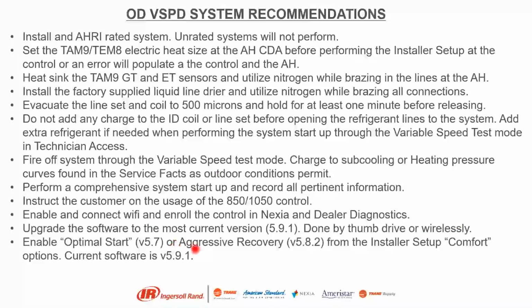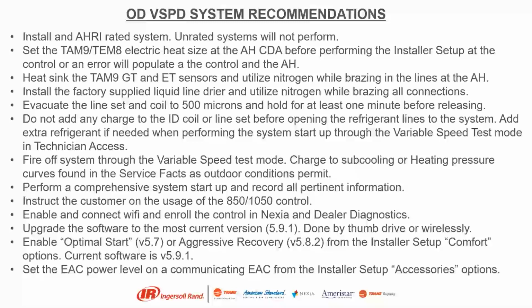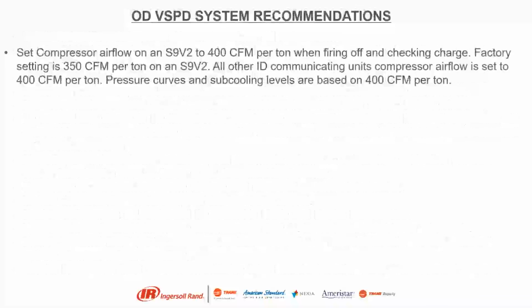Enable optimal start or aggressive recovery for heat strips. We do recommend setting that to aggressive recovery if we have heat strips, because it'll turn that heat strip on and satisfy the home quicker. Set the EAC power level on the communicating EAC. Set up accessories options. Well, we didn't touch on that too much, but you can set that to high to increase the filtration.